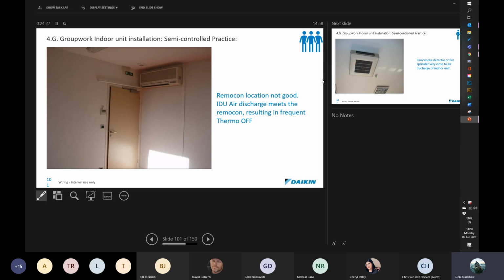And here are some installations that are probably not so good. Here we've got an indoor unit, and here's the remote controller on the wall. And obviously when this indoor unit's blowing air, it's blowing air directly onto the remote controller. Remember, wired remotes have a sensor in them, okay? And this is going to cause the unit to short circuit. So remember your placement of your remote controller.